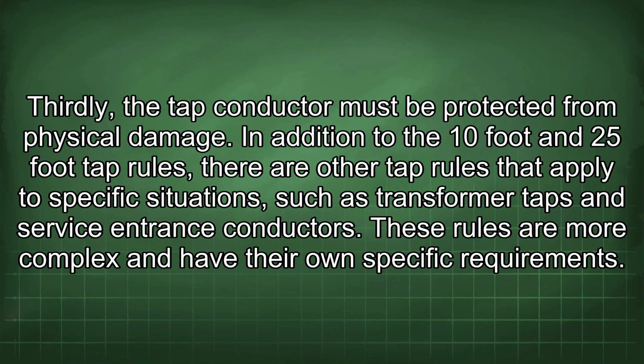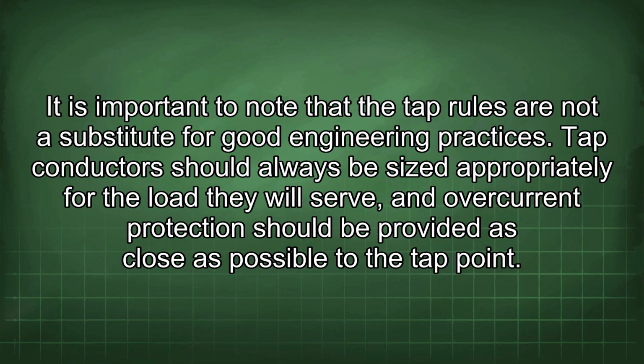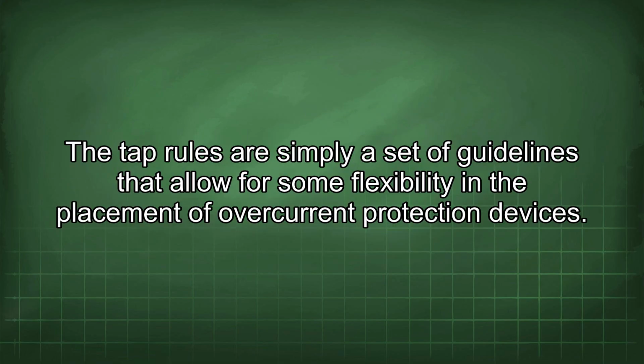In addition to the 10-foot and 25-foot tap rules, there are other tap rules that apply to specific situations, such as transformer taps and service entrance conductors. These rules are more complex and have their own specific requirements. It is important to note that the tap rules are not a substitute for good engineering practices. Tap conductors should always be sized appropriately for the load they will serve, and overcurrent protection should be provided as close as possible to the tap point.